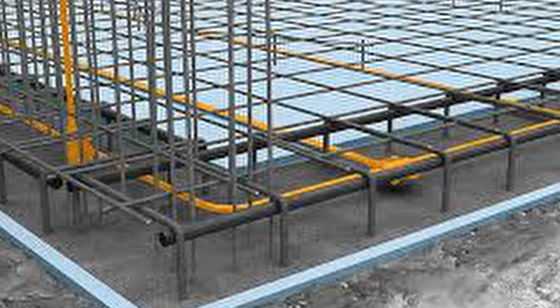Why does this work? Number one, the concrete retains the moisture. Number two, it's a large surface contact with the soil. Number three, it gives you an extremely low resistance. Number four, it's long-term stability, because the copper conductor is clamped to the steel reinforcement rebars, tested, and the concrete holds everything rigidly in place in contact with the soil - it is a strong earthing system. This is called foundational earth or ring earth. Once the concrete sets, you've created a permanent high quality earth electrode.